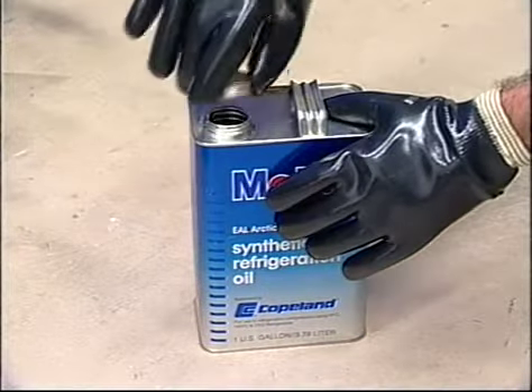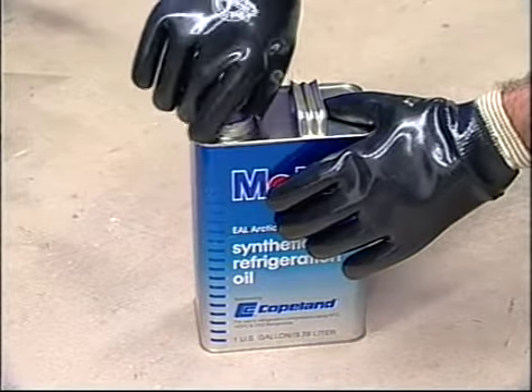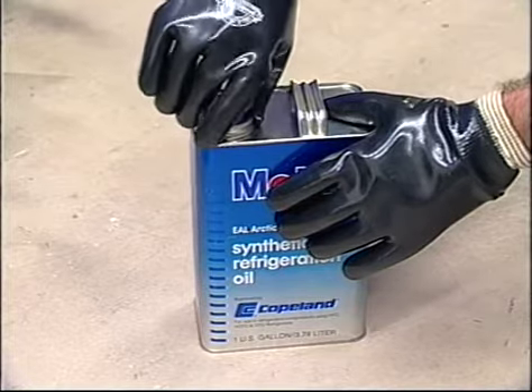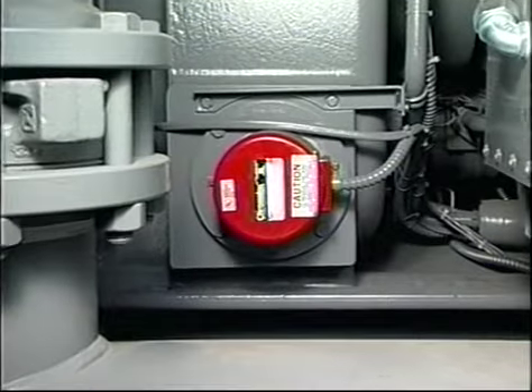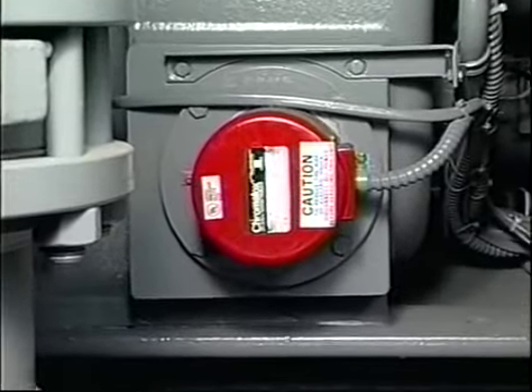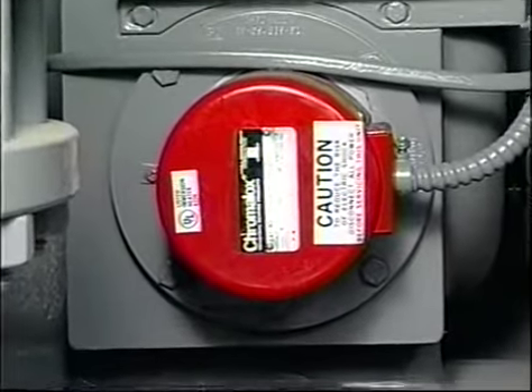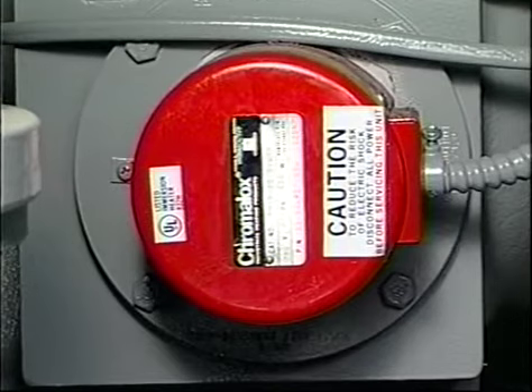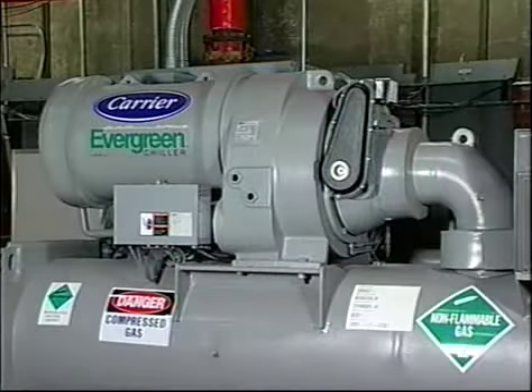The polyolester oils required for the new refrigerants are very hygroscopic, which means that they will absorb moisture faster and in greater quantities than oil used in the past. This means that any oil stored on site must be sealed from the atmosphere to avoid contamination. Also check to make sure the oil heater is keeping the oil warm when the compressor is shut down. The controls will not allow the compressor to start if the oil is not warm enough.